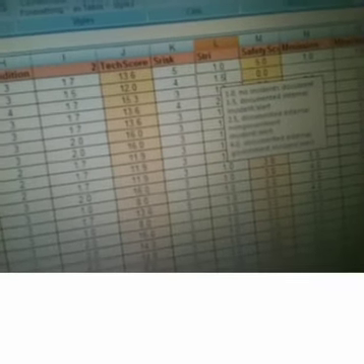Now we enter the risk. From 5, where death is possible with equipment failure, to 1, where there is no risk. We will say a bad paper cut is possible. So we enter a 4, possible operator injury. Then we enter a factor for reported problems. We track work orders by equipment, so we will enter a 1.5 for past problems.